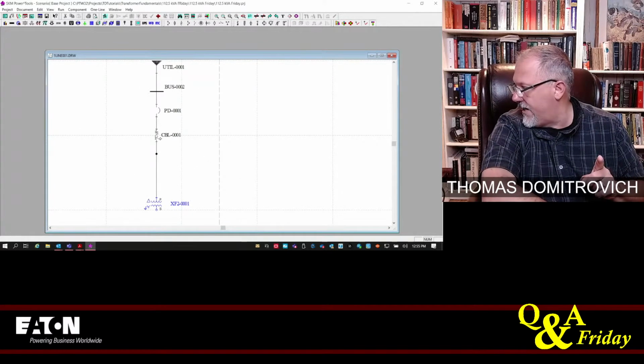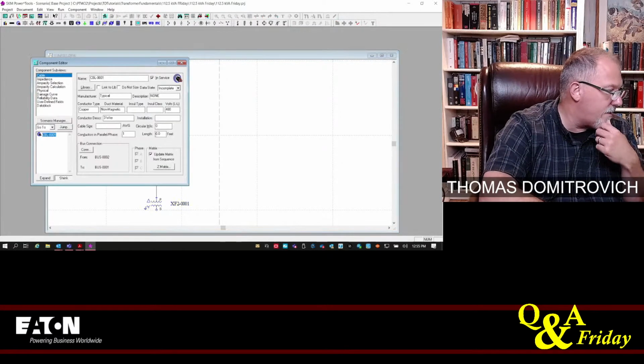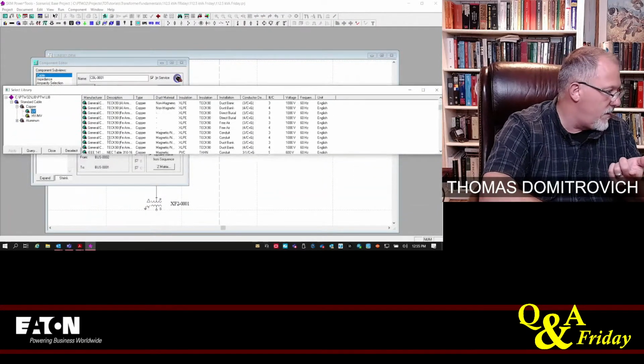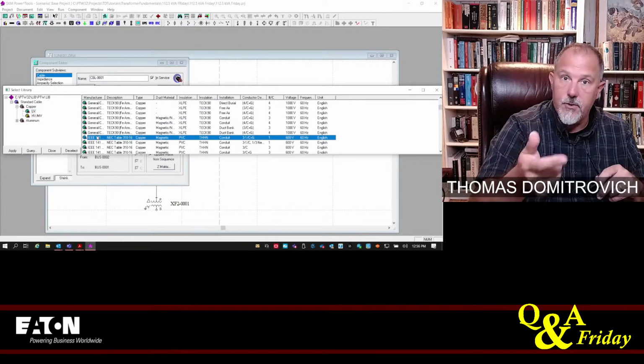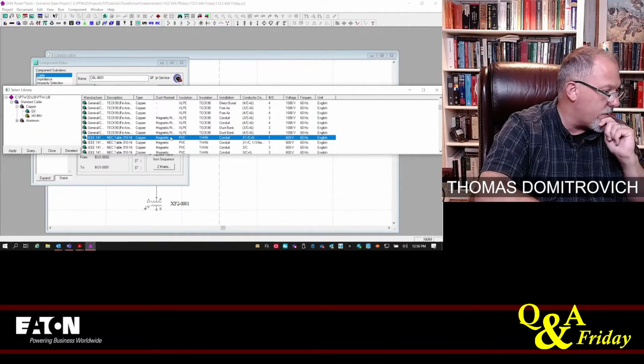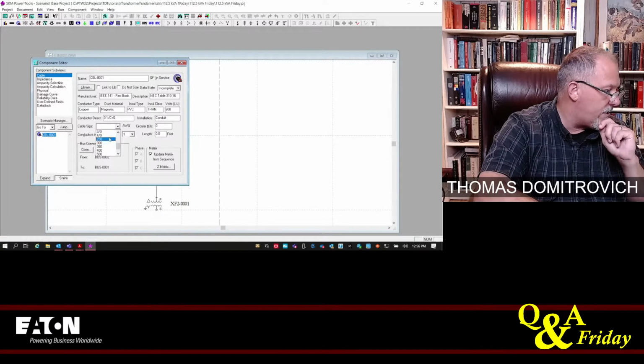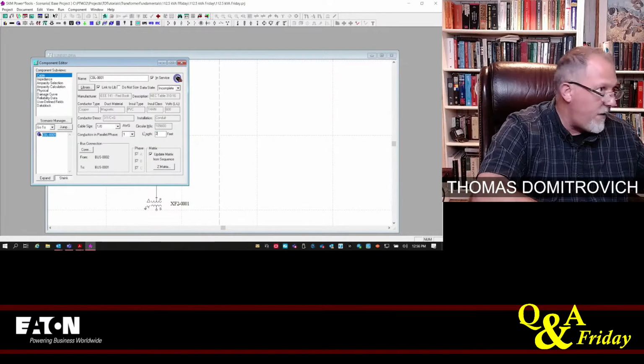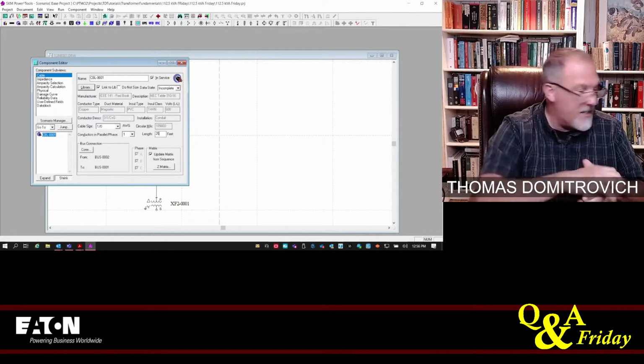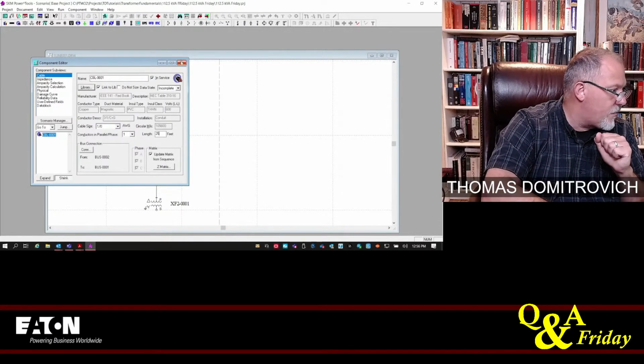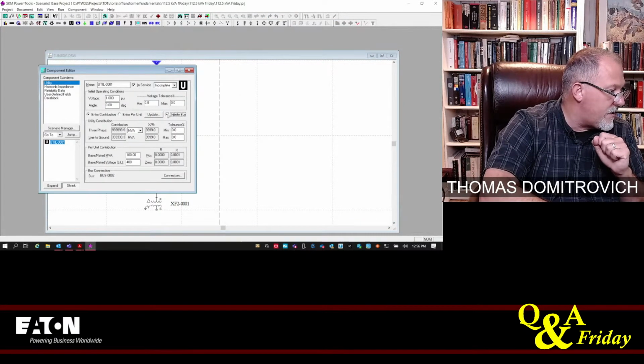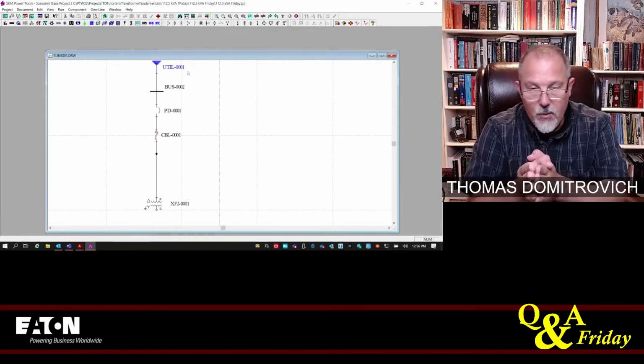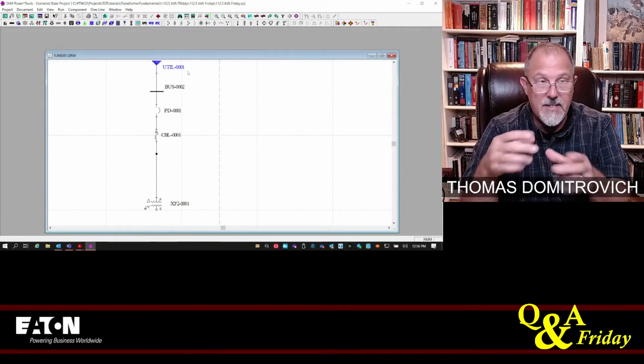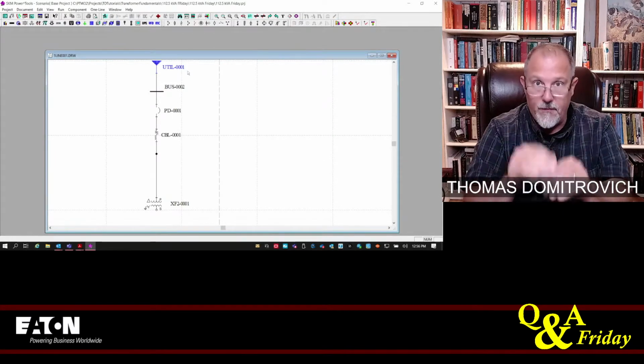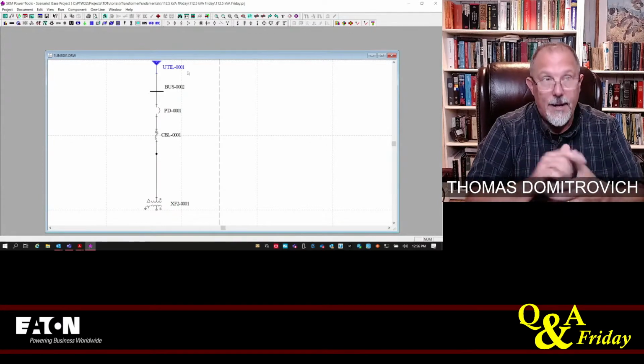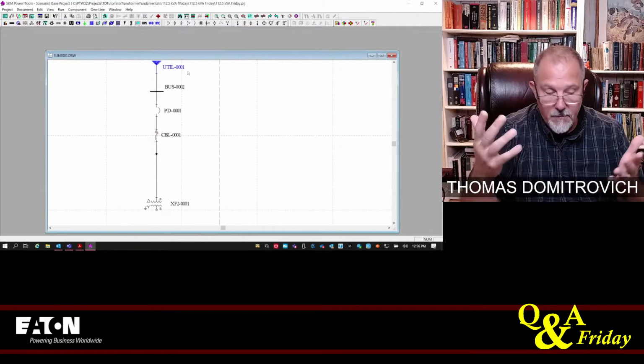Primary conductor, we're going to try to put a 1-aught conductor. I'll use copper. And since the delta is on the primary, I don't need a neutral, so it's a 3 conductor with a grounding electrode, the equipment grounding conductor. 3 conductor plus ground. And we said we were going to put a 1-aught in, and we'll make it 25 feet. 1-aught's going to be 150. We're going to see if we can get away with 150 amps. And so that is what we have there. We'll make that an infinite bus. That way, if I do infinite bus, when I do my selective coordination with the fault current values, I will know that my selective coordination pairs will work regardless of what the actual fault current is. So if I'm in the design phase, I want to make sure that that works. But now I run the risk of spending too much money on overcurrent protective devices, but you have to weigh that.